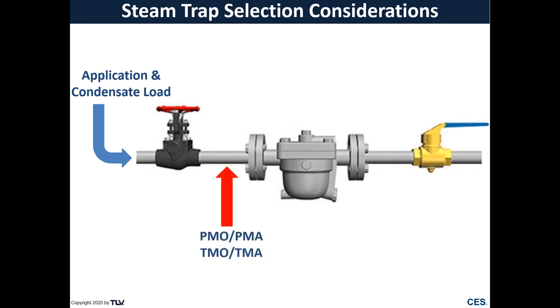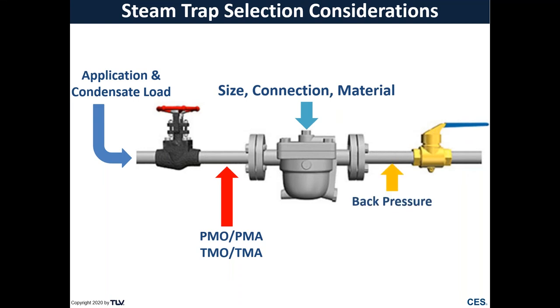Next, we're going to look at our operating and design pressures and temperatures, commonly known as PMO, PMA, TMO, and TMA. We'll also need to look at our size, connection, and material of our steam trap. The last thing we'll need to consider is, what is our back pressure or our condensate recovery line pressure?